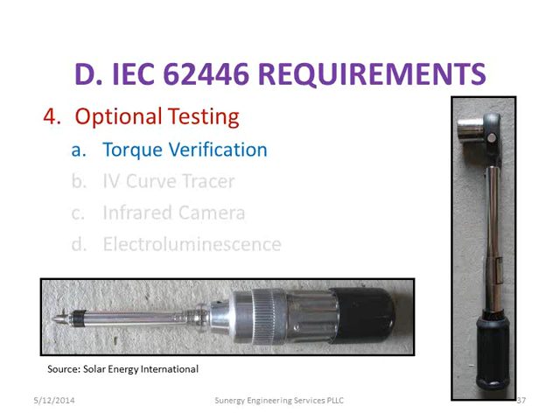And it seems like everybody goes towards the really high-tech kind of cool tools, although I don't really think that you need them that much unless you're required to in like a commissioning of a big bankability project, a megawatt project. They may actually require IV curve tracing of all the strings in the system. In fact, I have a couple friends that are going out and they're doing a big 50 megawatt SunPower project, and they're going to curve trace every string after the installation. So some banks are starting to require that.